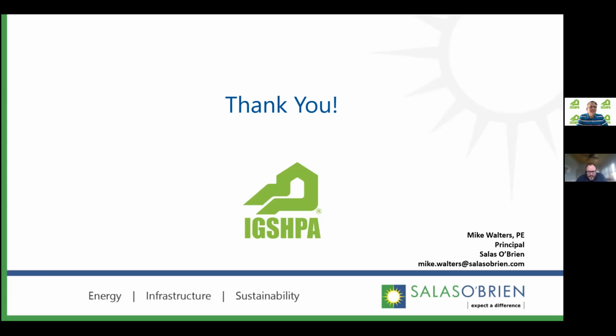There are no boilers or cooling towers on that campus, so the entire facility is a ground source heat pump system. I didn't highlight it, but they also have 10 megawatts of wind turbines a couple miles off campus, contractually inside their fence, and they take delivery of all that wind power. They've also deployed at least 1.5 megawatts of solar so far, and will continue adding solar resources to that site.